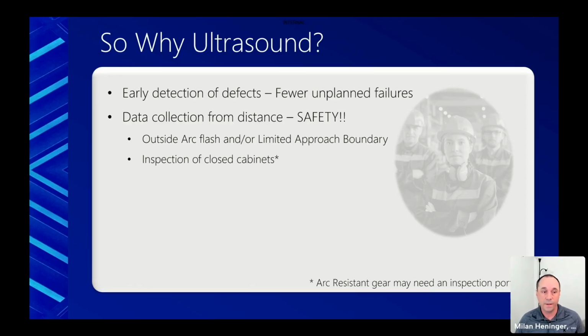I put a note in here that arc resistant gear does present a bit of a challenge, because we may need an inspection port. This really depends on the design of the gear. I've had success on arc resistant gear with ultrasound—it wasn't a big deal—but I've also had situations where it was sealed up so tight it was quite difficult to get good ultrasound without an additional inspection port.